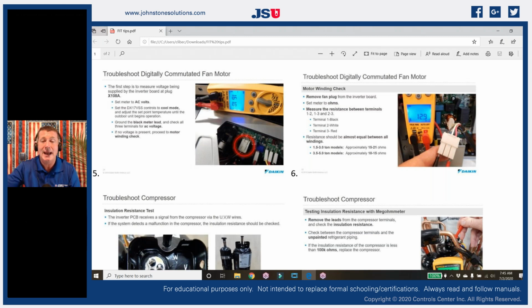So we just simply check those on our particular chassis. On our Daikin FITs, we really only make 2 chassis. So from 1.5 up to 3 ton, the actual chassis is all the same. It uses the same condenser fan motor. It just uses a different capacity compressor, really, because even the control boards are the same. And then from our 3.5 to a 5, it's a different chassis, but it's got a little bit larger condenser fan motor. So we can take our meters and we can ohm between pin number 1 and pin number 2. And if it's on the smaller chassis, it'll be between 15 and 21 ohms. If it's on a larger chassis, it'll be between 10 and 15. And then I'm going to go between 1 and 3 and 2 and 3. And those should all be the same, right? Because it's a 3-phase motor, they should have the same windings to them.